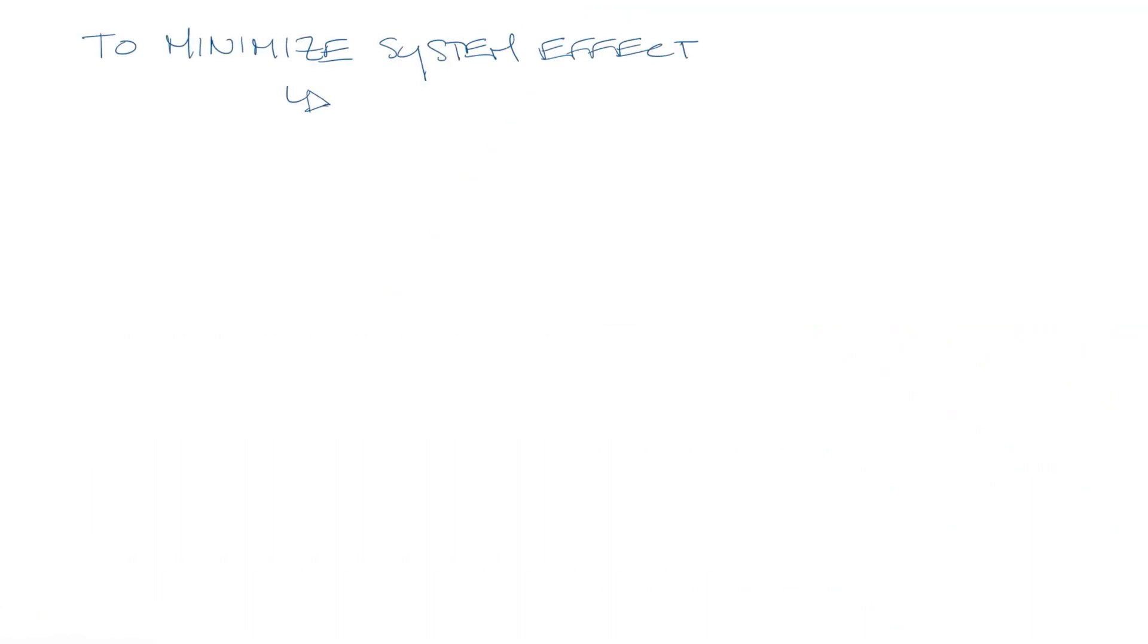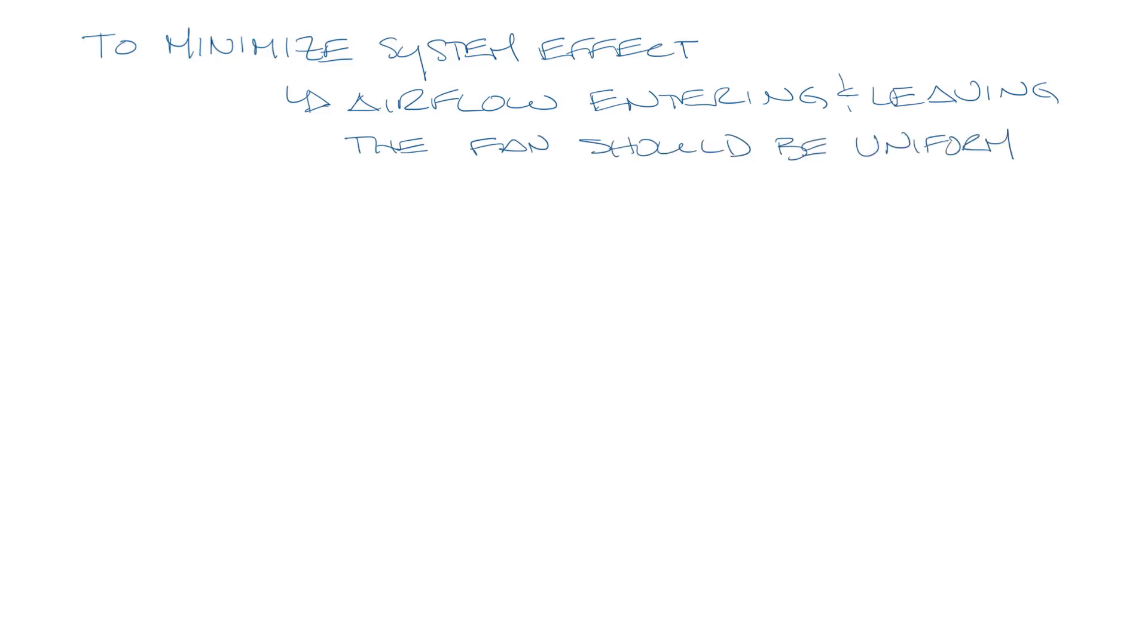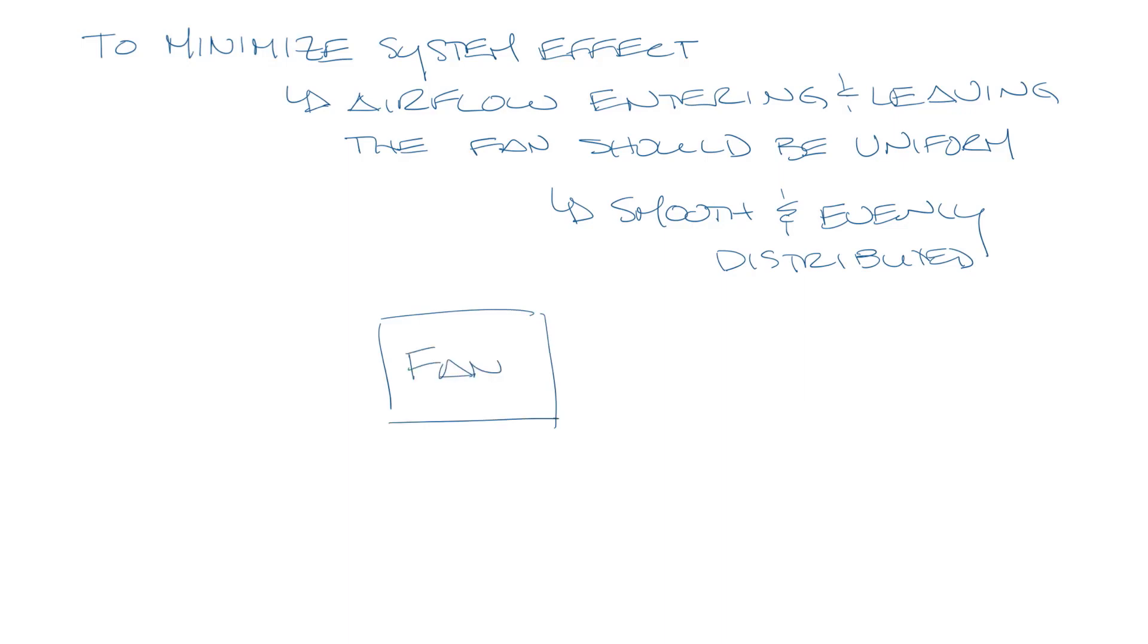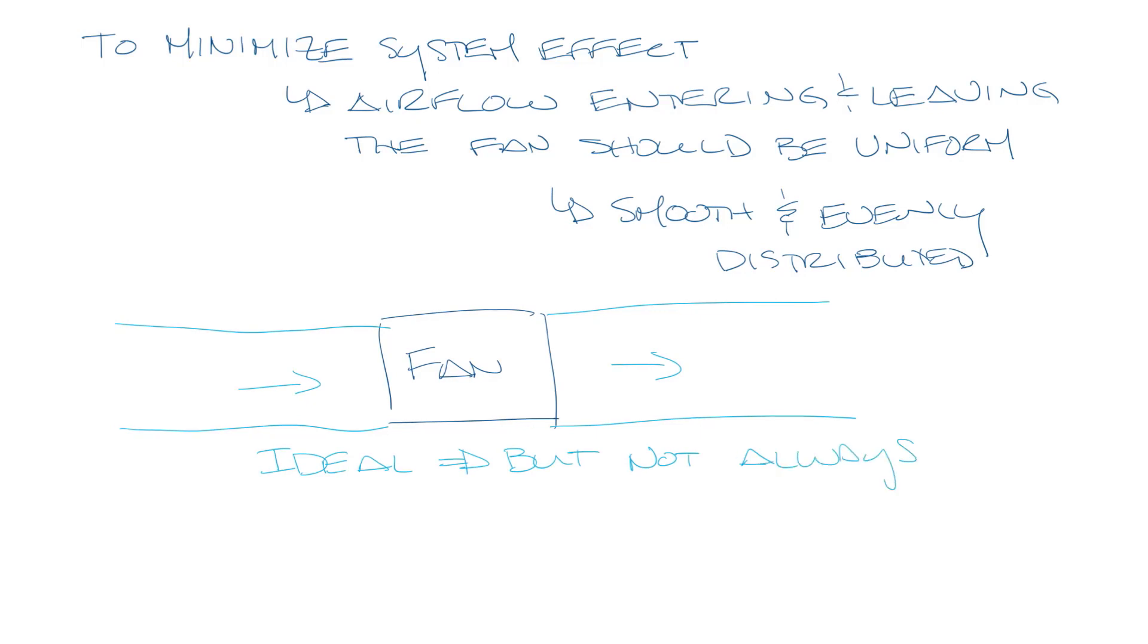To minimize system effect, the airflow entering and leaving the fan should be uniform. It should be smooth and evenly distributed. So ideally, your inlet and outlet conditions would look like this in and out of your fan. This is ideal, but not necessarily realistic.